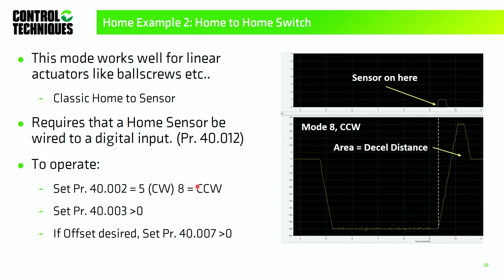That's home to sensor using mode 8, which moves the motor counterclockwise as viewed from the motor face. Mode 5 does the same thing but in the positive direction. If you want an offset, plug it into menu 40 parameter 7. Home in place and home to sensor together cover probably 80% of applications.